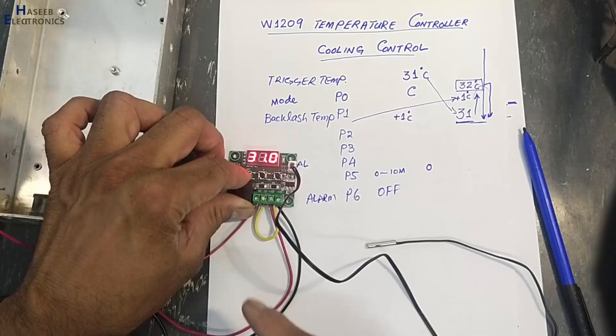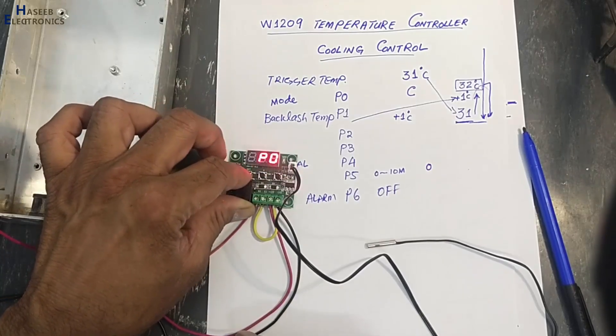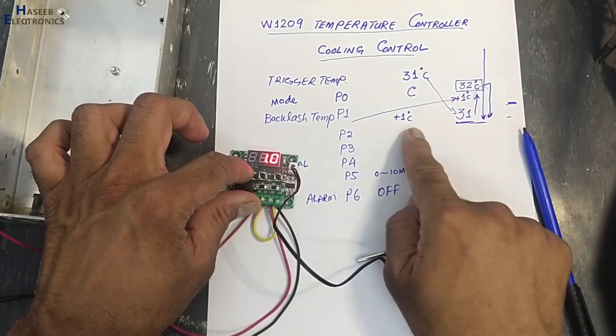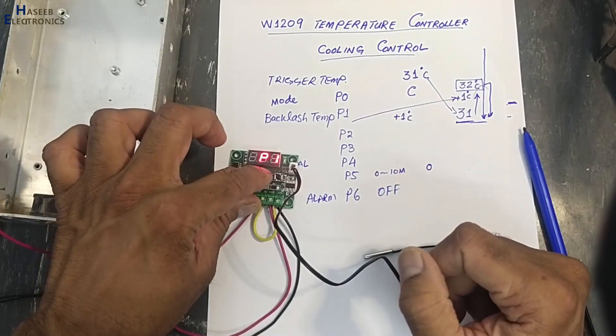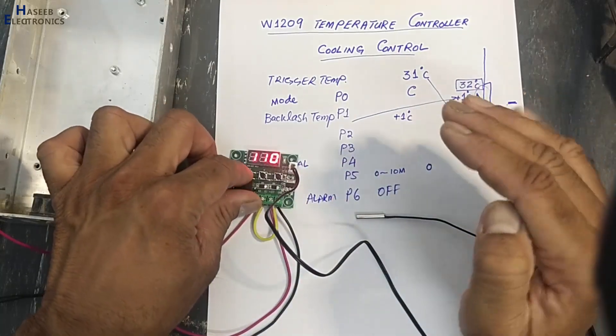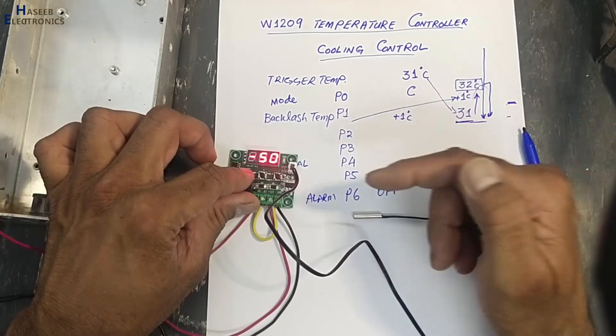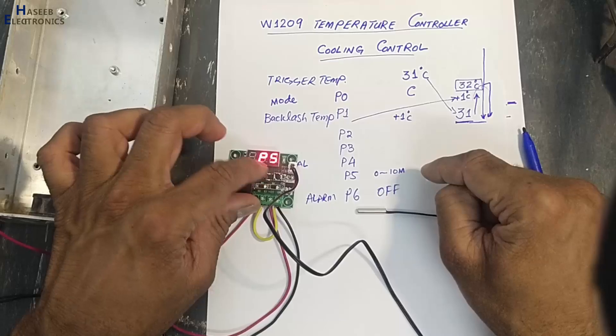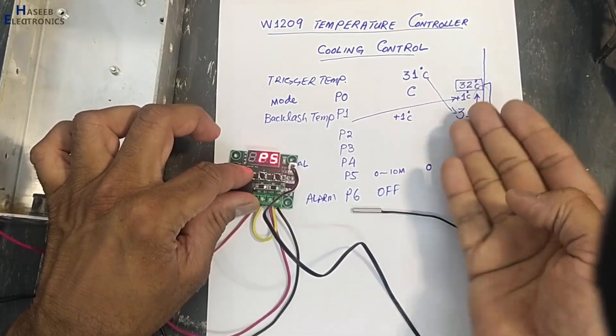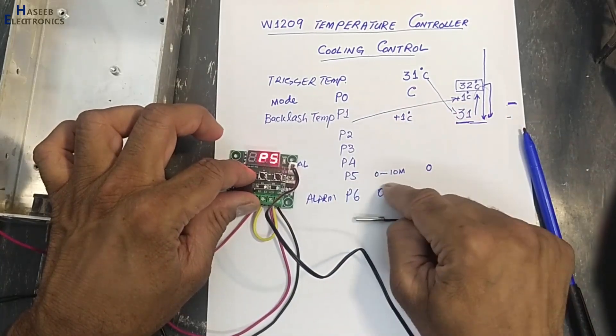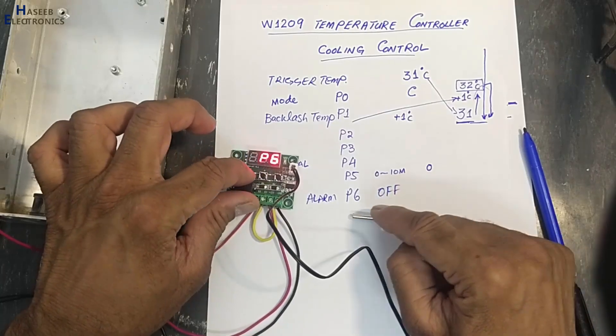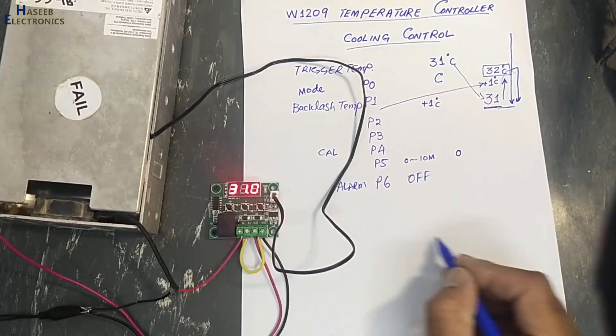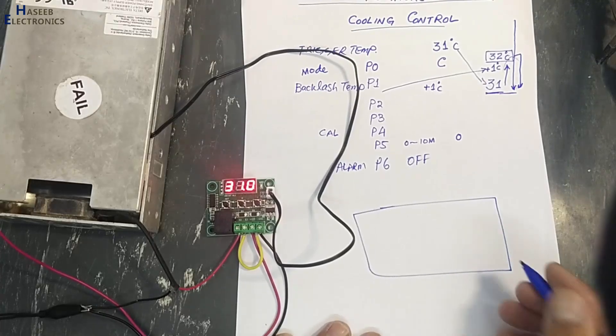Let's check all settings again. Trigger point temperature is 31°C — that's OK. P0 is in cooling mode. P1 backlash is 1°C — good. P2 maximum is 110°C — no need to change. P3 minimum is minus 50 — no need to change. P4 calibration is 0. P5 delay time is 0. P6 alarm is off.